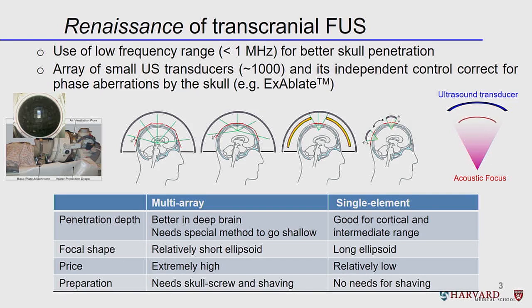in the high intensity range. On the other hand, you can utilize a single element transducer that may use an acoustic lens, or just shape its transducer surface with a slight curvature so that it can zoom in the acoustic pressure wave onto a specific brain area. So multi-array transducers offer advantages over the single element by delivering a much tighter focus into deep brain areas. But the single element can also do a lot of things. The multi-array transducer unit is a little bit expensive and pricey, and it also requires surgical grade patient preparation. For instance, it requires shaving of the hair, as well as putting in a skull screw. So it may not be that applicable for routine use in an outpatient clinical setting. So one can seek a hybrid approach, which may take advantage of the two.